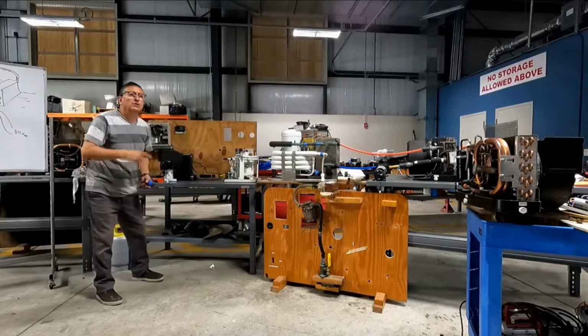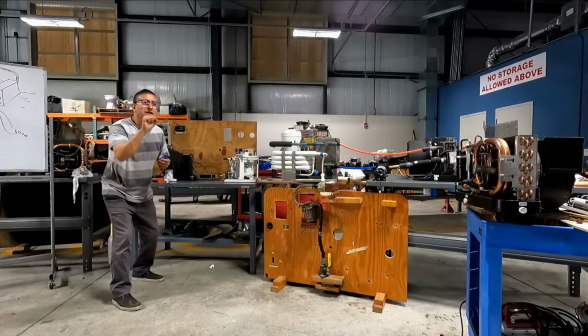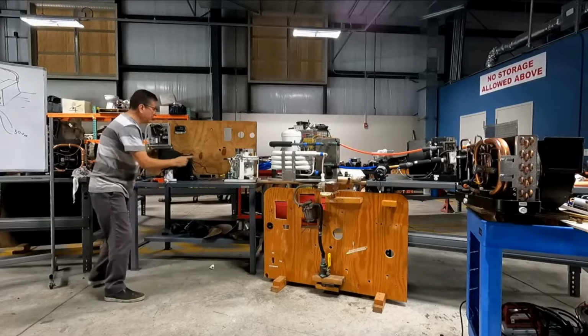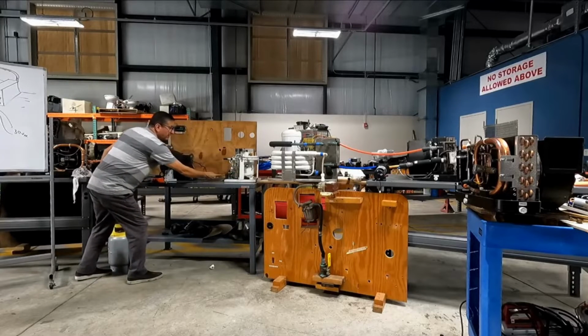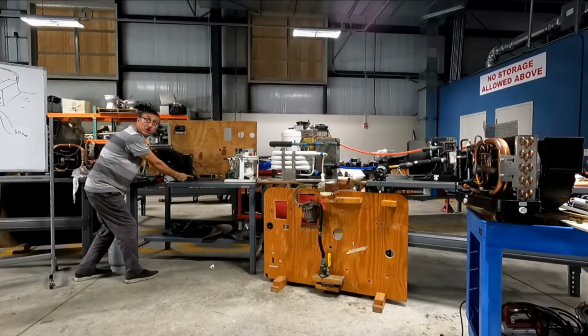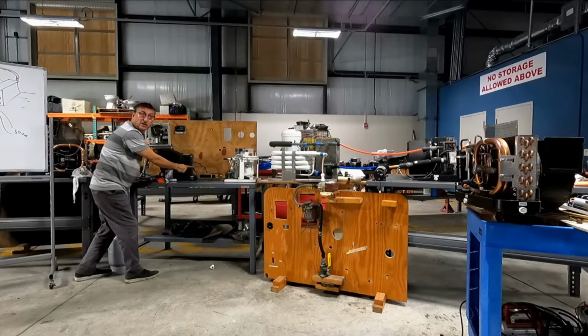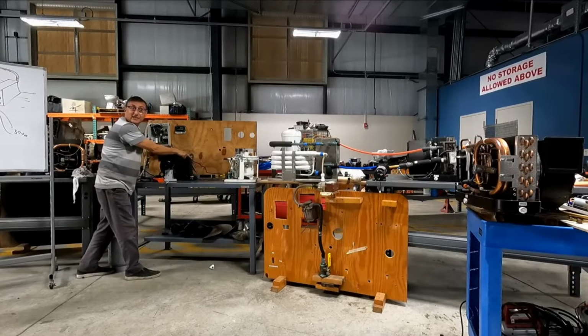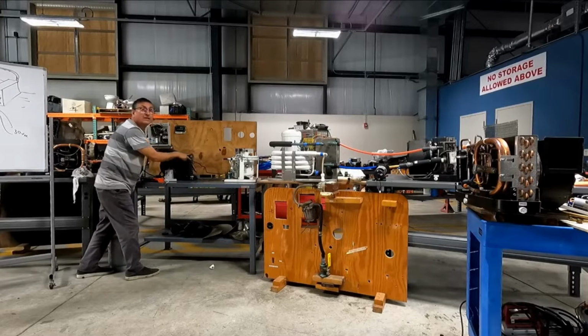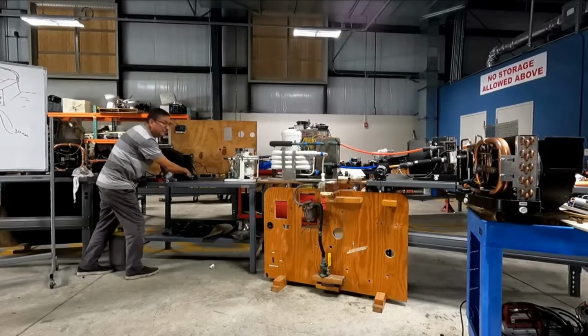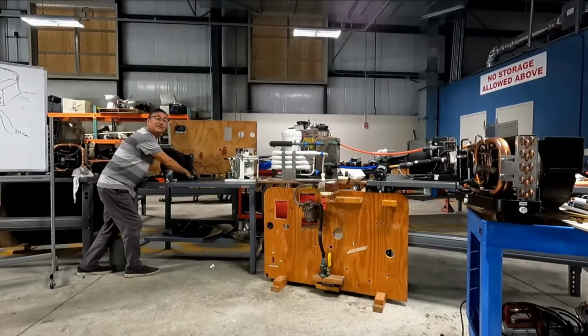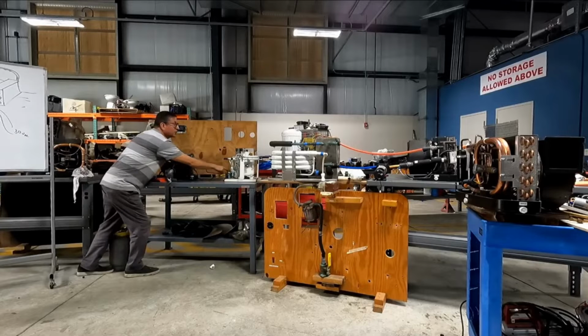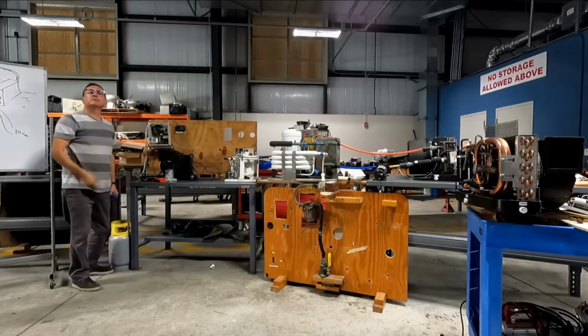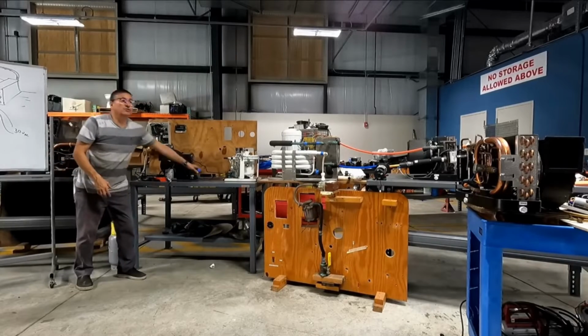The cycle starts in the compressor. The compressor receives the signal from the thermostat, and the compressor starts to compress the refrigerant. In the discharge of the compressor, you have refrigerant at high pressure, high temperature. Yes or not? Yes. The refrigerant passes through the dryer filter, and after that, what is this? The capillary pipe. What happened here with the refrigerant? After the capillary pipe it reduces temperature and reduces pressure. Low pressure and low temperature, and it enters at the bottom of the evaporator and starts the process of evaporation of the refrigerant. And the refrigerant goes out here fully evaporated and returns to the suction port of the compressor, and the cycle continues. This is the refrigeration cycle. Yes or no? Yes.